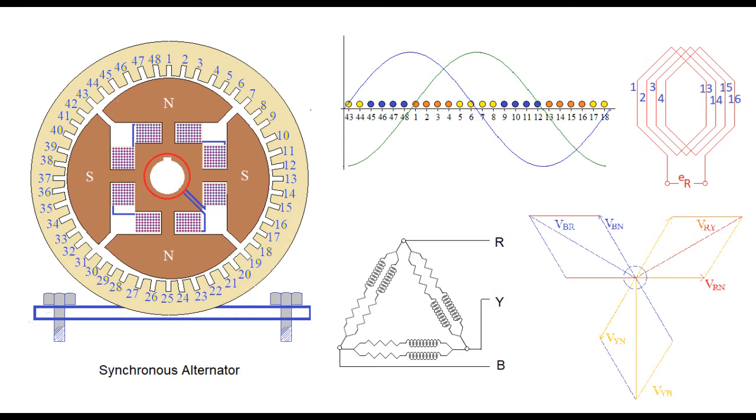The synchronous alternator that we are considering now has poles on the rotor side, and their windings are provided with DC voltage. The excitation windings are connected to a DC supply through two slip rings shown on the slide. When full rated voltage is applied and rated current passes through the excitation windings of the alternator, rated magnetic flux is established in the air gap between stator and rotor.